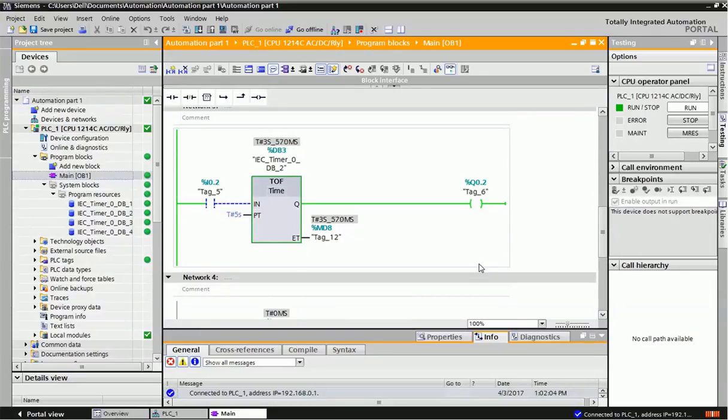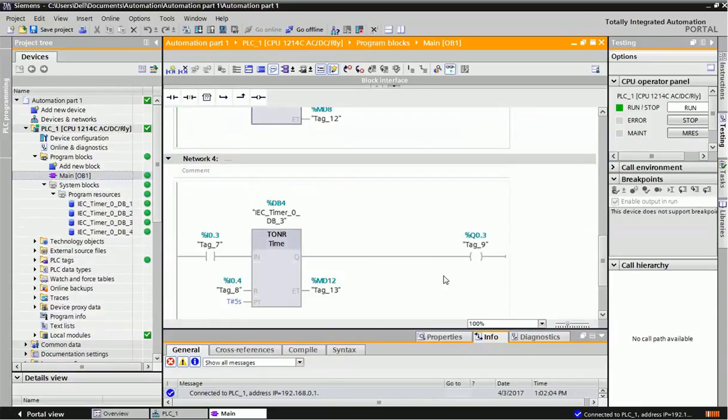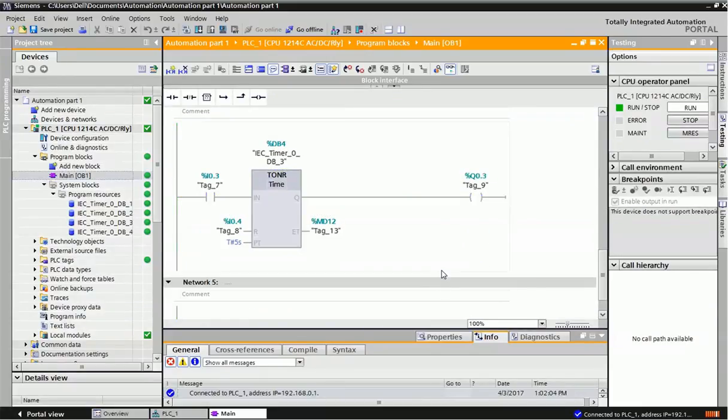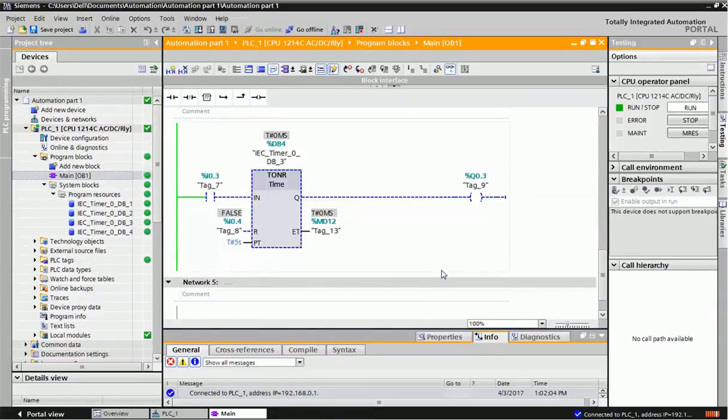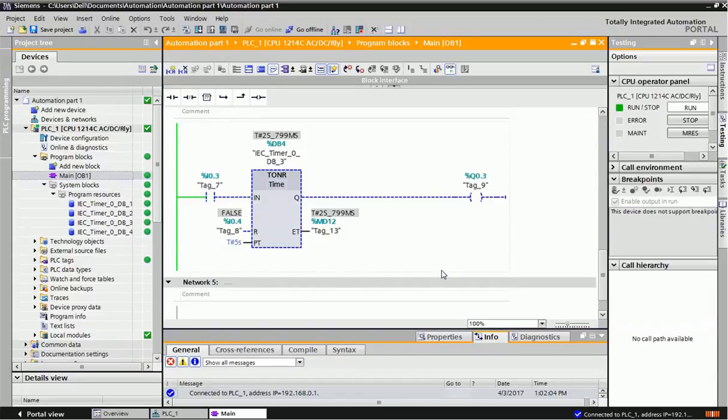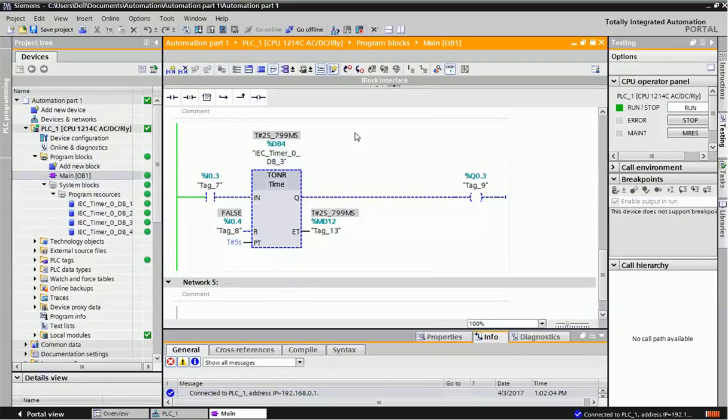The last timer is the Retentive timer (TONR). This timer has memory - it remembers the time from where it stopped. Once again, I give input I0.3, and it starts from the holding time. After the preset time, this output will be on. In this timer, you need to reset the timer after completing the operation.